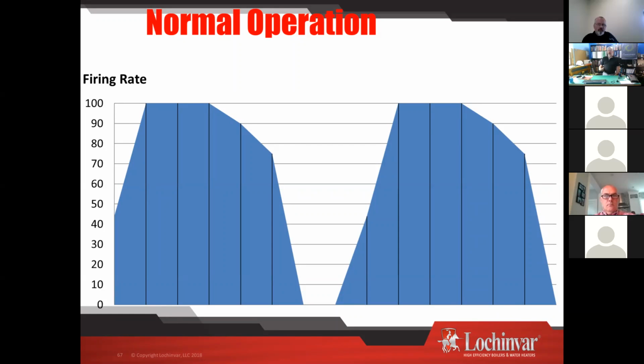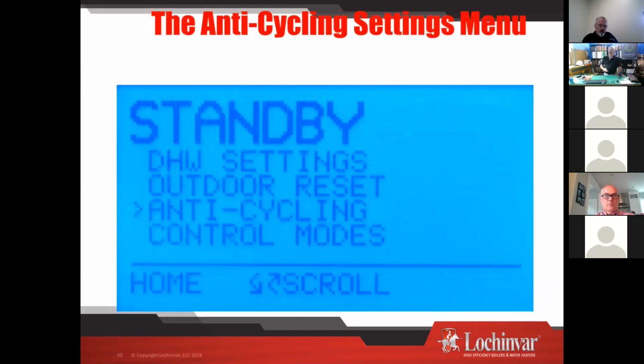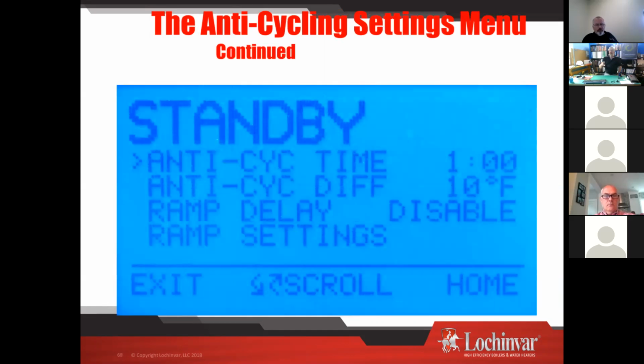Where would you do that? Well, let's go to the scenario where now when we're sizing up boilers and we're looking at things, you know, people have a jacuzzi tub. I need an 80-gallon indirect. I need 200,000 BTUs for my 80-gallon indirect, but my house is like 50,000 BTUs. Or I had 4 zones, but geez, 8 zones will be better. You got to slow the boiler down. This is what ramp delay gives us the ability to do. So we jump into our anti-cycling menu. We go down here to ramp delay and we're going to enable it.